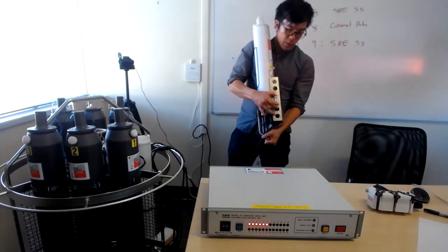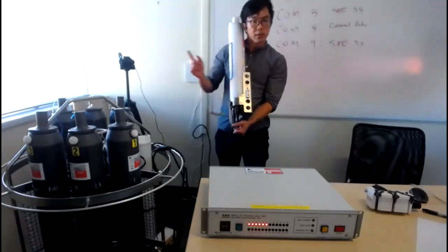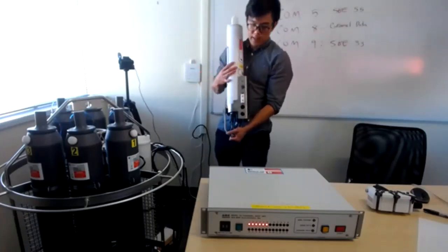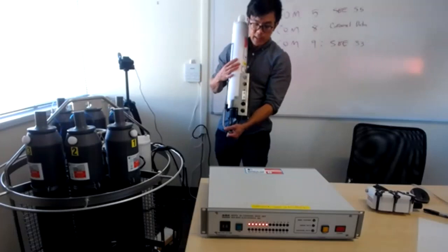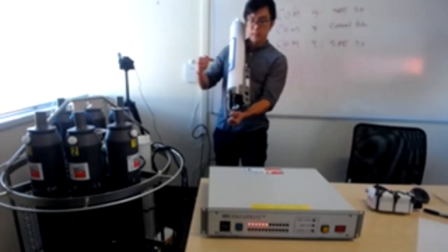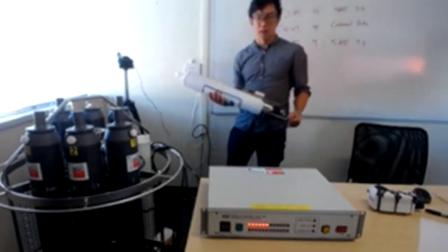So in this case, as we saw when I was demonstrating the elapsed time, when we armed the 55, it started the countdown timer and it fired bottle number 1 and gave us the message no CTD data. That's because I did not put the switch to on. So once I flipped it to on, hex data in output format 4 was sent from the CTD to the 55. And in that case, when the next bottle's fired, we got a bottle confirmation, and we did not get that message saying no CTD data. So good question. CTD needs to be logging and outputting data before you start the autonomous cast.